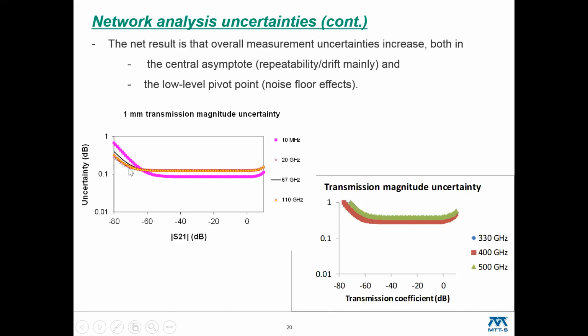This lower corner is really determined when the noise floor takes over. If you look at the level at which noise floor is adding about a half dB of uncertainty, that's moved up a bit, maybe from minus 85, minus 90 to somewhere in the minus 75 dB range. So it moved a little bit. And the upper corner is from compression. While we showed earlier that the absolute intercept point might have gotten worse, for these two systems the default power is a lot lower at the higher frequency. So that's where that wash came into play.